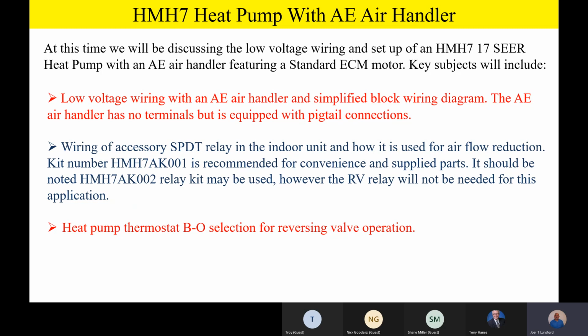Our kits are recommended for convenience and all the supplied parts, but if you have to field manufacture, in other words, if you just need to buy a little peanut relay and a biflow filter dryer and make up all the wiring, it's no big deal. You can do it in the field if you need to. It should also be noted that the HMH7AK002, the 002 relay kit, may be used. It actually has 2 relays on the board. However, the RV relay will not be needed for this particular application. So I like to consider the 002 relay kit really as kind of a universal relay kit, in the fact that it has 2 relays on it. And if you need to, you can use that kit because you're only going to be using one of them on the AE air handler in this example.